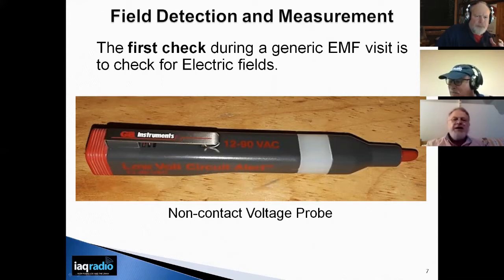If on the other hand they have armored wiring, which may look something like this with a flexible armor around the cable, then the electric field emission will be reduced by 99%. So when I use that non-contact voltage probe, if I get an immediate response on approach to the wall, I know what kind of wiring there is.